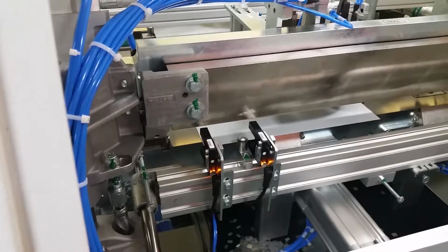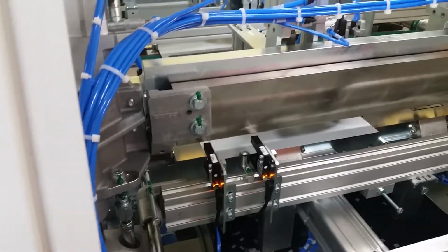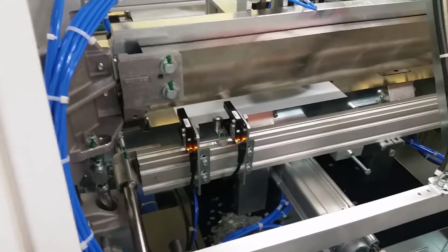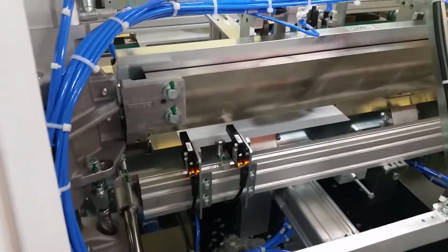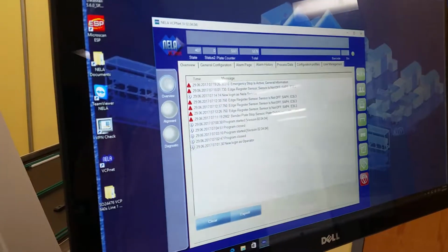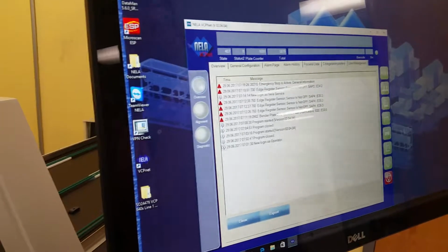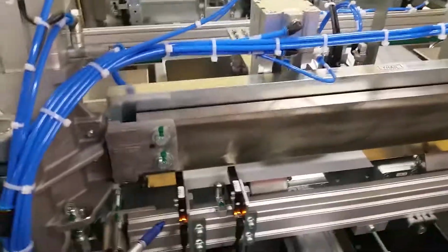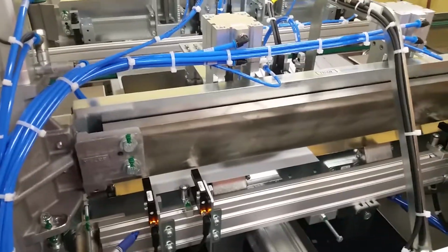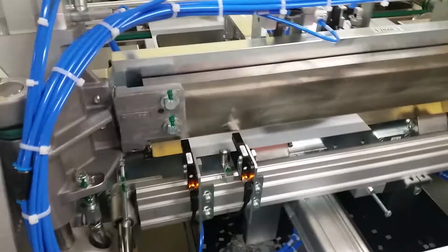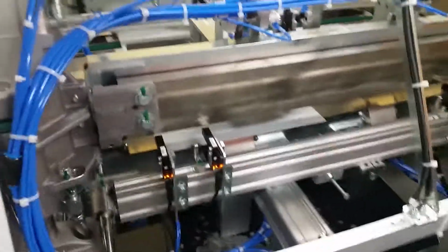Same thing. Now if you set it so close from back to back plates, it may get some failures, and it'll record it up here in the alarm history as a SAP sensor alarm. It'll tell you which SAP sensor you're in there with. If it doesn't get this SAP sensor right, it's going to reject the plate if it's in normal mode, in either vision or edge.